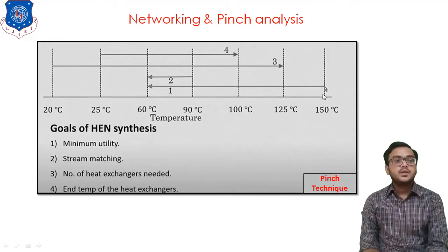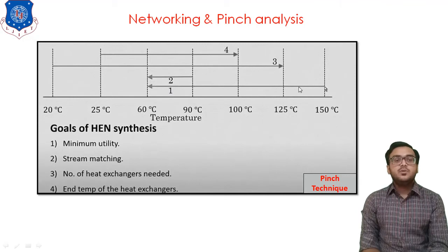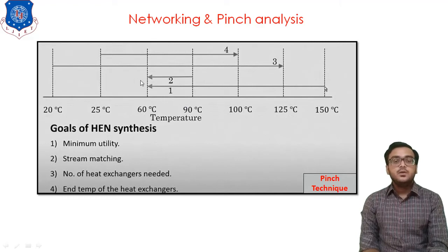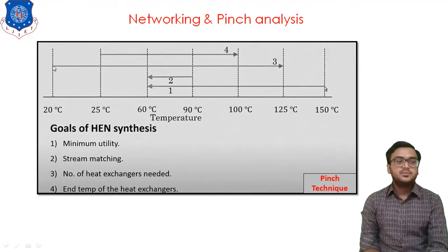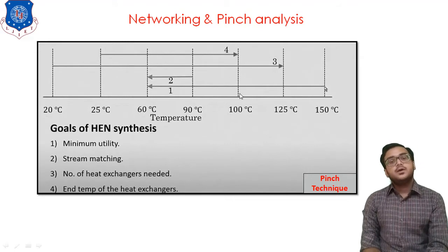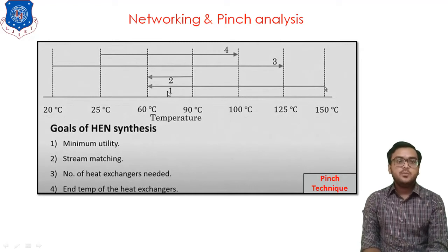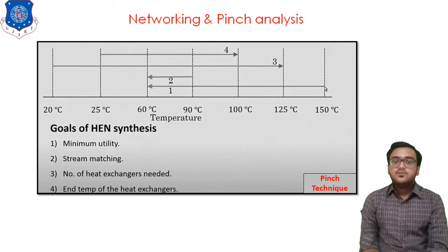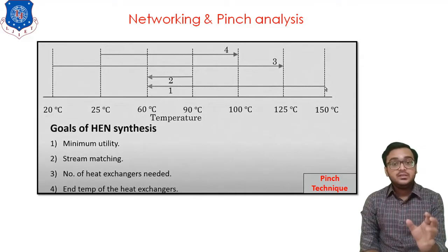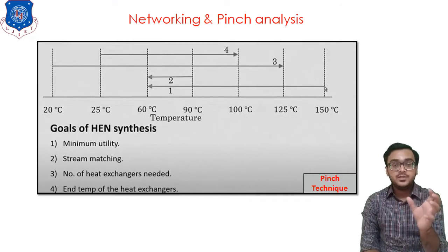For stream number 1, we want to reduce temperature from 150 to 60 degrees — plot a line from 150 to 60. Then for stream number 2. For stream number 3, a cold stream, we require to increase temperature from 20 to 125 degrees — plot this line. Similarly for stream number 4. Observing the temperature profile diagram, all four streams are exchanging heat in the zone where the temperature profile is between 60 and 90 degrees.